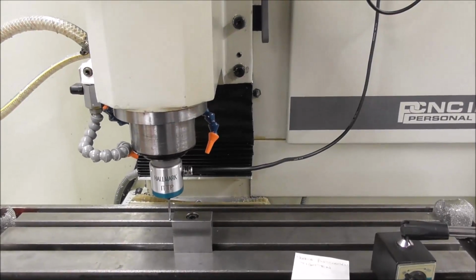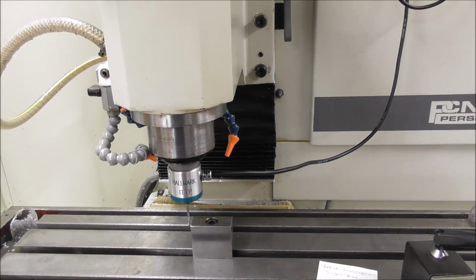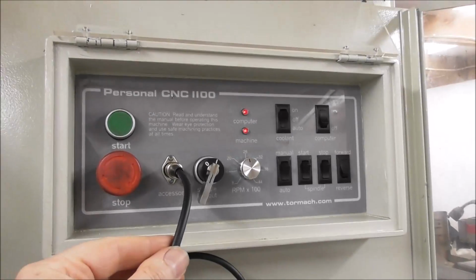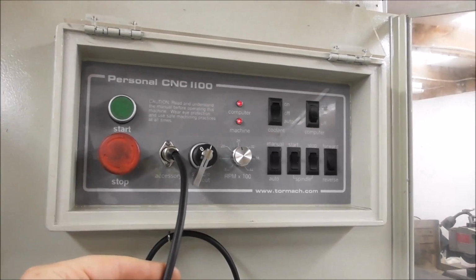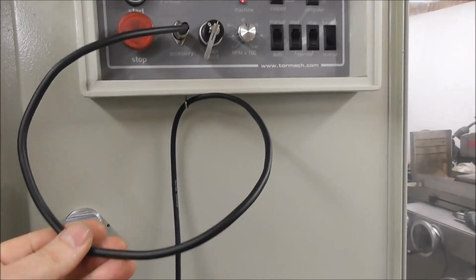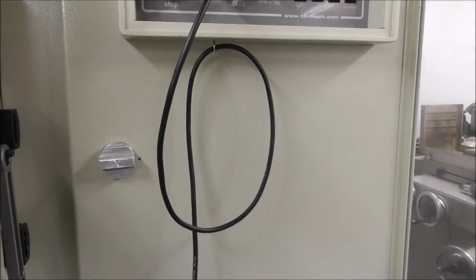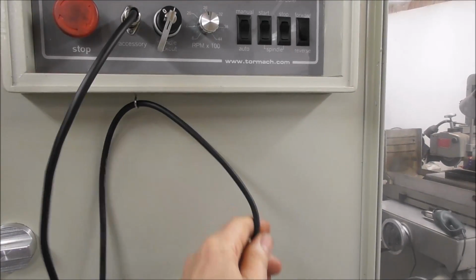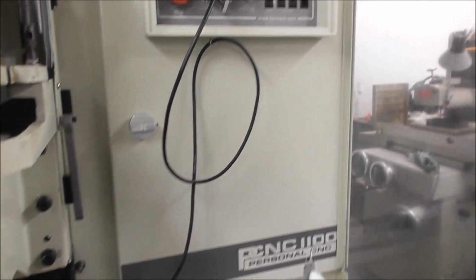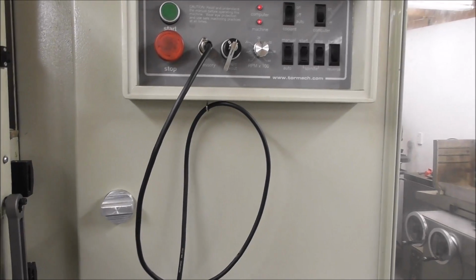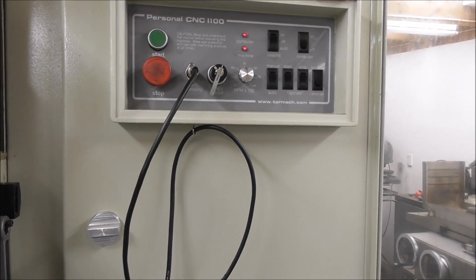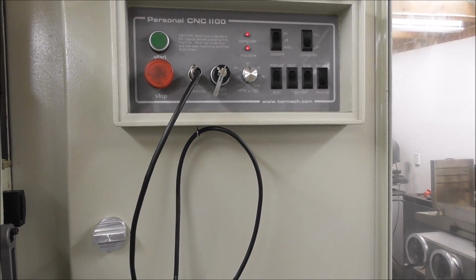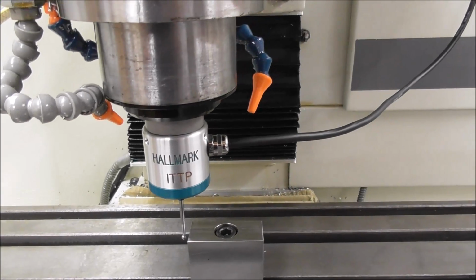Okay, so once we've set the probe concentric and entered the diameter in the tool table, we're now ready to plug the probe in to the accessory socket, a 5-pin DIN plug, and think of some way to tidy up your lead or your cable so it's not draping in the cutting oil or chips. And you might want to have a little block for your probe that carries the probe in its as-use orientation, so that the gel stays in the little reservoirs.